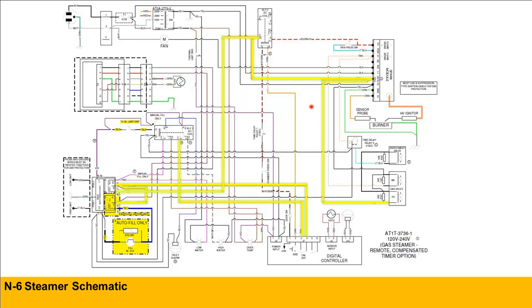And at that point, we'll actually focus our attention to the DC circuit. But for educational purposes, what we're going to do is say that we don't see the red light, we don't have any static pressure. So we have a break in the AC circuit, so now we've got to figure out where that break in the circuit is. So once the unit's turned on, obviously anything we see with violet and yellow, that's basically telling me as soon as I get power, I have power going to my component.